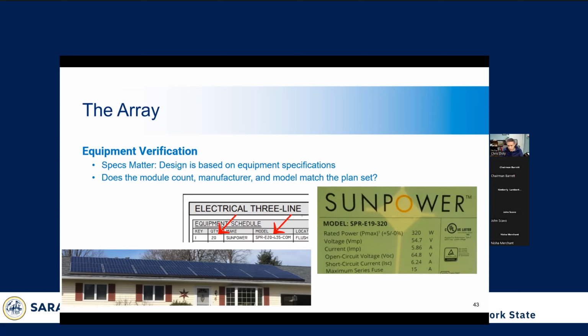And so a good example of this is maximum system voltage, or the open circuit voltage. They can be higher for higher wattage panels, or even the same wattage modules from different manufacturers can have different open circuit voltage. And all of your circuit sizing, overcurrent protection, and wiring size are designed based on the energy production from the panels, obviously. So you don't want to just assume that the wiring and the other system components are still compatible.